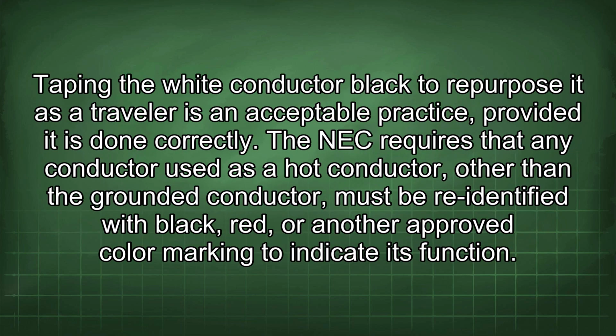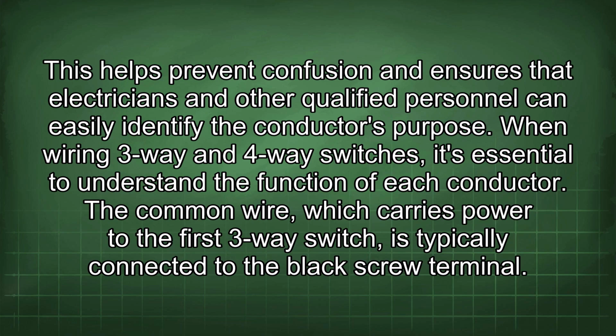Taping the white conductor black to repurpose it as a traveler is an acceptable practice, provided it is done correctly. The NEC requires that any conductor used as a hot conductor, other than the grounded conductor, must be re-identified with black, red, or another approved color marking to indicate its function. This helps prevent confusion and ensures that electricians and other qualified personnel can easily identify the conductor's purpose.